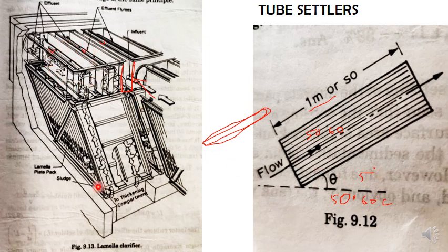So in this, what is going to happen is, imagine this. Yeah, this itself is 5 to 6 degree. Now water will enter from the bottom and it will exit, and during this period the water is moving up with minimum velocity, whereas the suspended particles in it will adhere to these pipes, or they will hit them, their velocity will become zero, and in turn they will try to settle down. Similarly, if the inclination is more, the same procedure is going to happen.